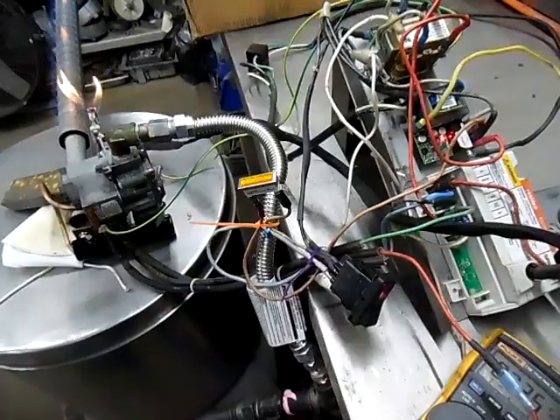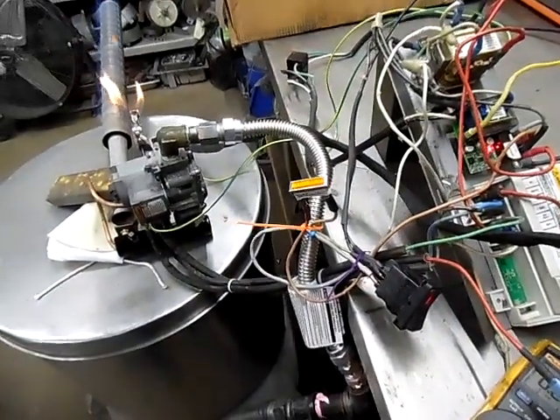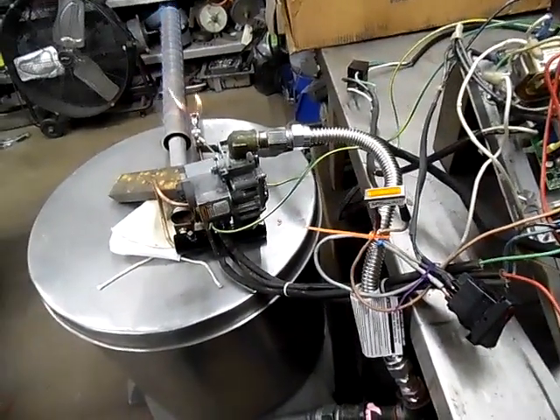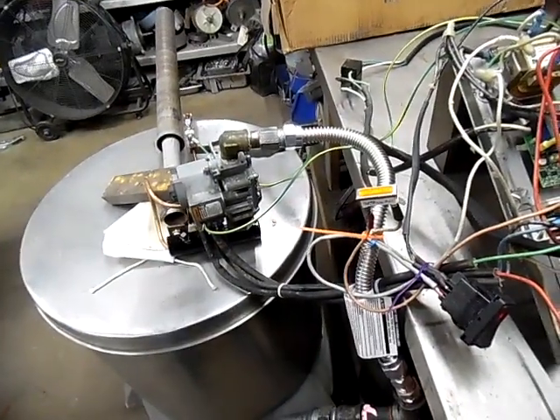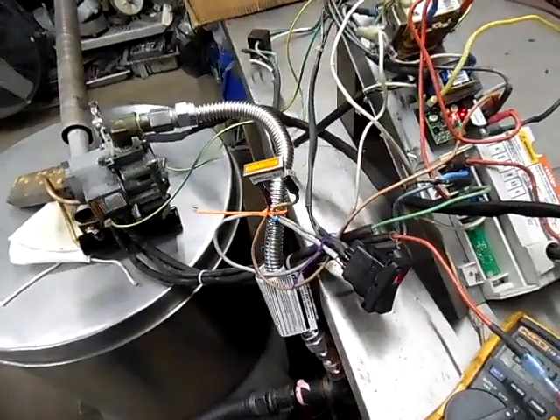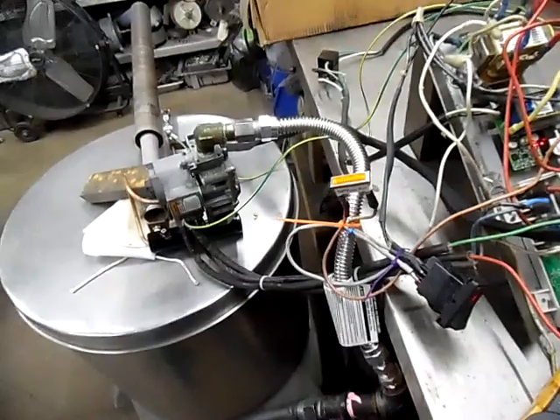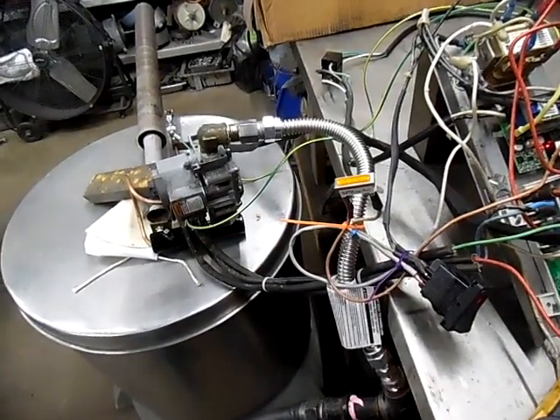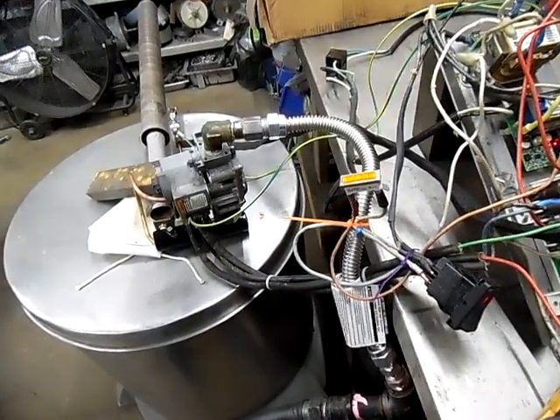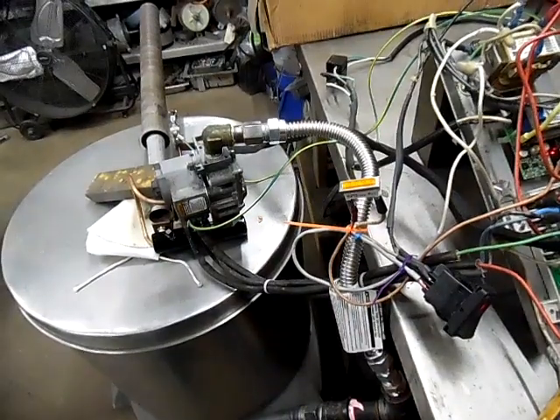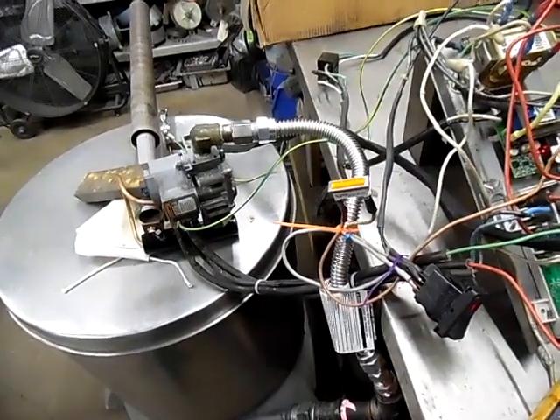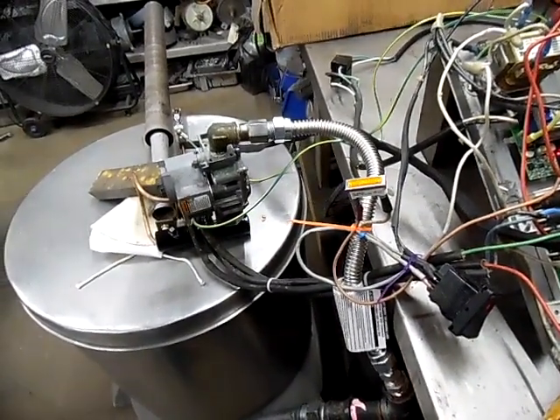Let's turn this back off. Now watch what happens when I turn the gas off. Let's say that we just lost the flame. If the box is working correctly, it'll immediately go back into restart. But it can't restart because I didn't turn the gas valve on, so no pilot. But if your box is working correctly, it'll go back into restart and start sparking again. And that's what it'll do when it cycles on the temperature.